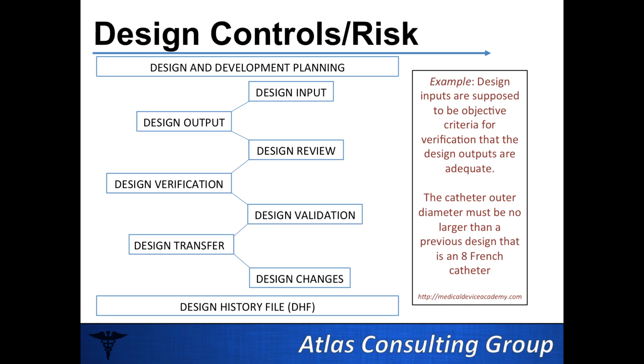All right, so moving on to design, and this will answer some of your questions too about how the design process works and how it creates a static device. So you start off, you need a design and development plan. You need design inputs, which are subject to objective criteria for verification that the design outputs are adequate. So a catheter outer diameter must be no larger than the previous design, that is an 8 French catheter. So if you have a design input that says this cannot be larger than an 8 French catheter, your design output has to match your design input.